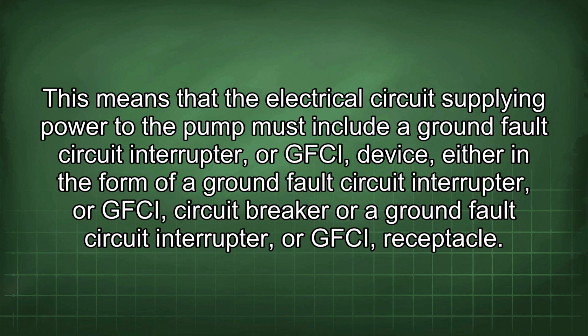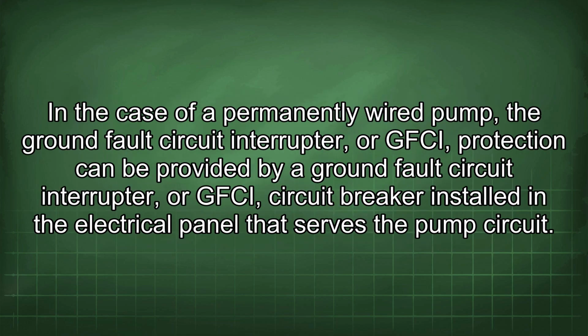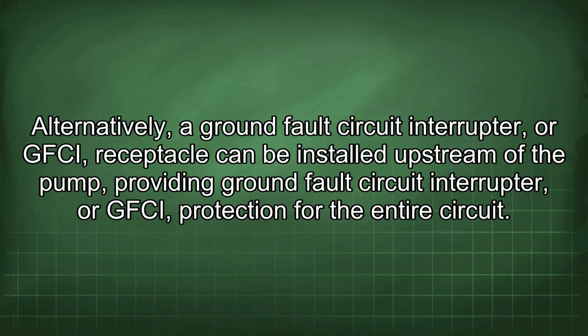In the case of a permanently wired pump, the GFCI protection can be provided by a GFCI circuit breaker installed in the electrical panel that serves the pump circuit. Alternatively, a GFCI receptacle can be installed upstream of the pump, providing GFCI protection for the entire circuit.